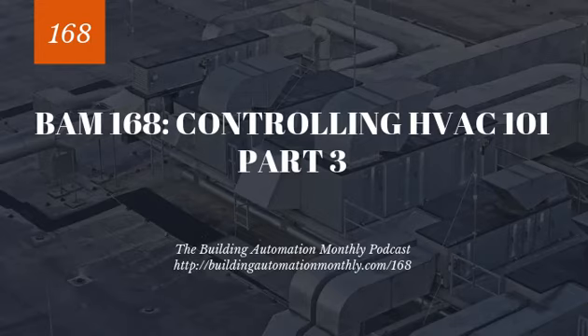By utilizing economizer, by raising discharge air temperature set points on air handlers, you're able to reduce the demand on the secondary or primary chilled water loop, thus reducing the delta, the difference between chilled water return and chilled water supply. I really hope that makes sense. I know it's kind of a more advanced concept, but it's an important one, especially when you get to really large tonnage plants.